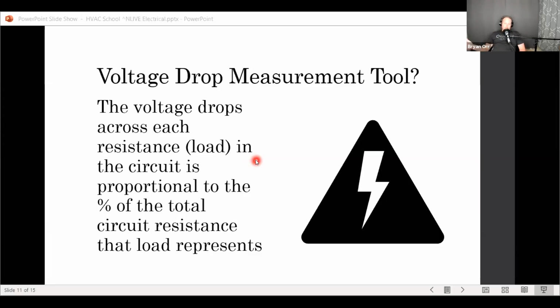So in the case of a 240 volt circuit, that would be between L1 and L2. In the case of 120 volts, that would be between L1 and neutral. In the case of 24, that would be between hot and common, right? And so each one of those circuits, parallel paths, only has one load. And so when we measure across the load, we're measuring generally 100% of the voltage drop, or nearly, because almost all the resistance is going to be in the load.